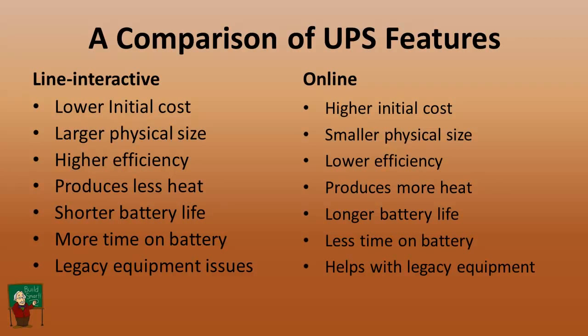Probably the principal downside of the line interactive would be that a UPS is sometimes required to deal with legacy equipment issues. Modern electronic equipment, computer equipment, is able to handle brief outages, has a reasonable input power factor, and doesn't require the kind of power conditioning that the older equipment did. So if you had older equipment, you can have problems both with the operation from line voltage fluctuations that are totally isolated with the online UPS, and also that equipment can cause power factor issues with the utility, with the power that's coming in to the building. So the online can totally isolate that legacy equipment and prevent problems both in the building and problems with the equipment itself. So this would be sort of a comparison.